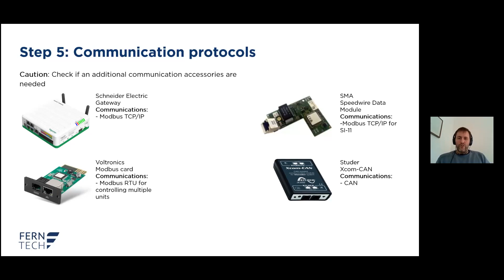Now going into a bit more detail, but it's all about the same thing - when it comes to communication protocols, make sure you have the communication interface and know how things will be connected to each other, especially in rather complex mini grids, and whether you have the information on the communication protocol, because sometimes a new device needs to be added. To do that, the supplier of the monitoring solution will need all the information, including the list of how to read the registers from the communication protocol.